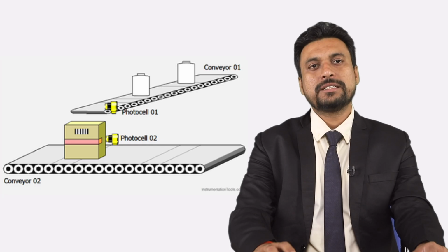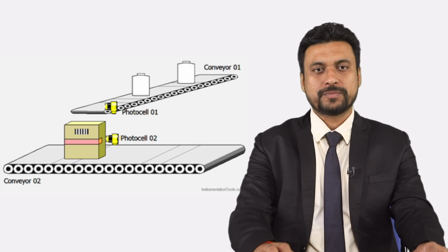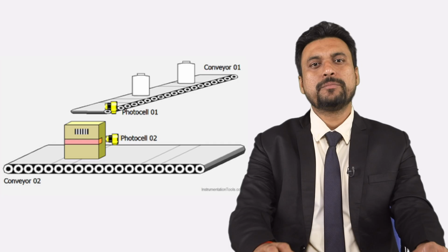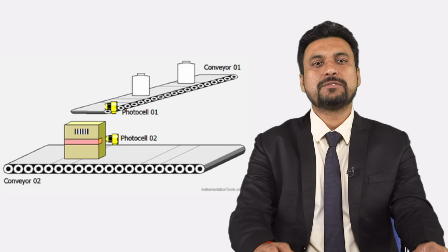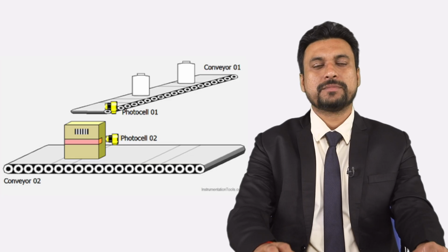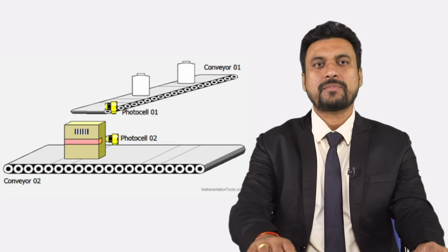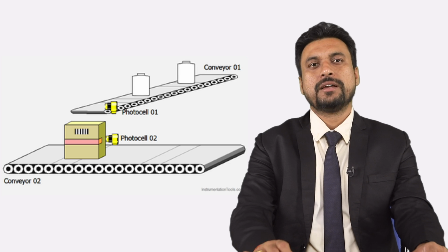My second conclusion is that this is the main drawback of down counters, because the done bit operates when the accumulator is less than the preset value. It means in the previous example we wanted the process to happen 5 times. That's why I set my accumulator equal to 5. But the actual process happened a 6th time, and then the done bit will operate, right? I think you understand the operation of down counters.